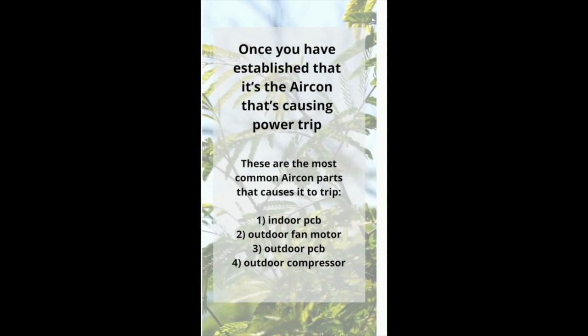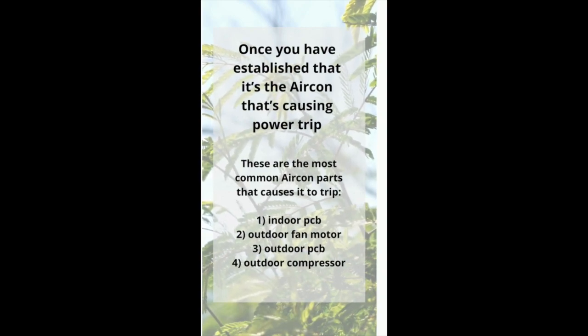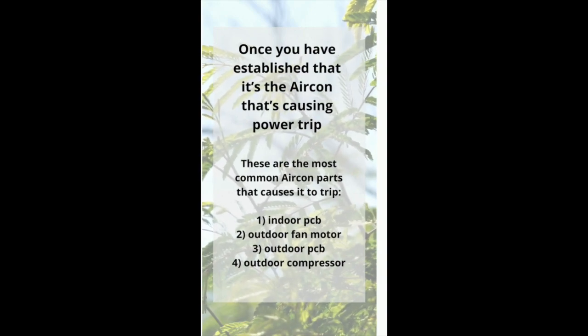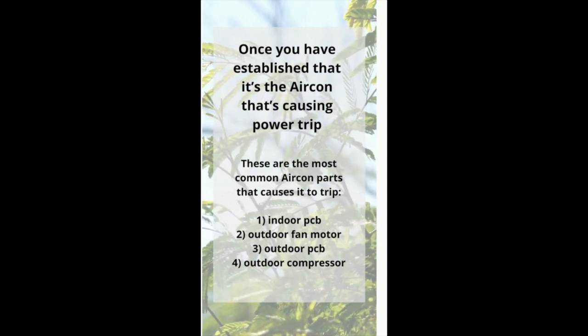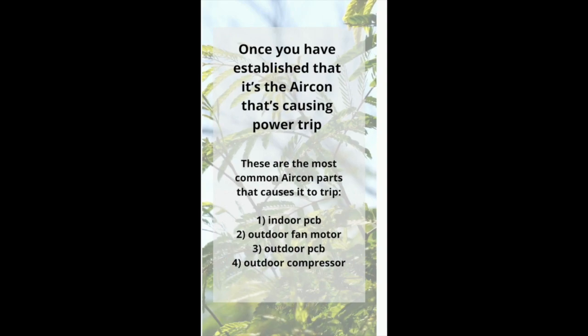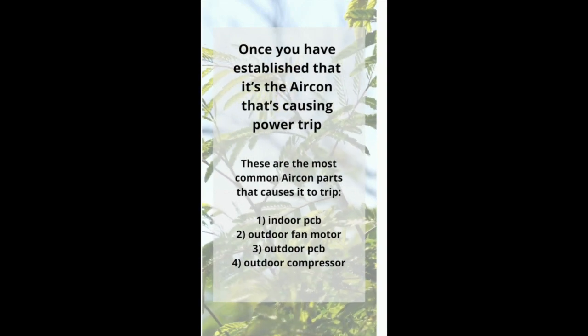Once you have established that it is the aircon that's causing the power trip, these are the most common aircon parts that cause it to trip: it could be the indoor PCB, outdoor fan motor, outdoor PCB, or outdoor compressor.